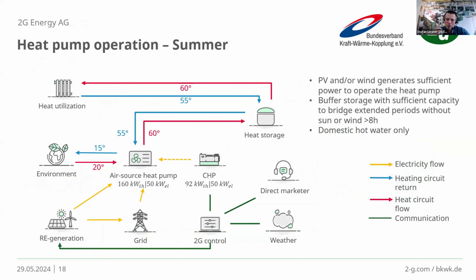And then, coming back from CO2 emissions, energy costs and the thermodynamics, from a year or month perspective there are also lots of benefits. I don't want to step too much into the details of this sheet, but what should be the message? I was mentioning at the beginning, in one of my first slides, what the gas consumption in Germany is with a very hot summer and a very cold winter. In summer, as you can see here, the CHP in the middle only has a kind of backup function electricity-wise. With an increasing amount of wind and solar, the time where the CHP delivers heat in summer will be reduced and reduced. So maybe a backup function for electricity, but less and less operating hours with heat in summer.